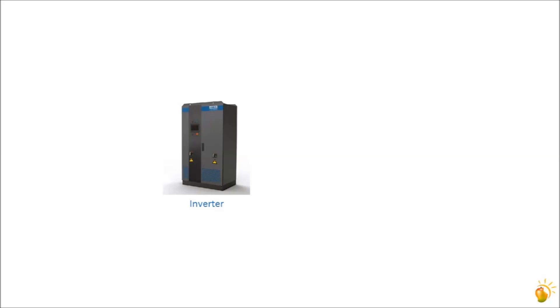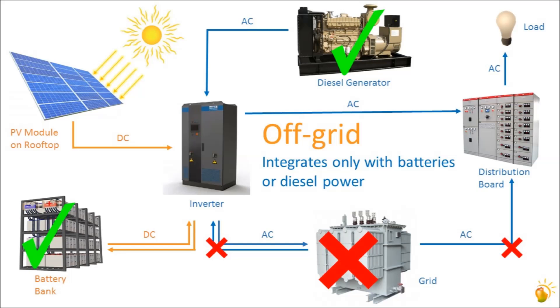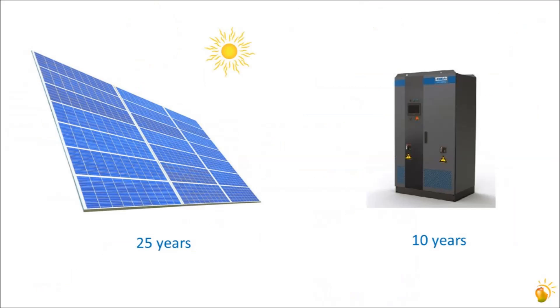The three types of solar plants boil down to three types of inverters: the grid-tie inverter that integrates only with grid power; the off-grid inverter that integrates only with batteries or diesel power but not with the grid; and finally the hybrid inverter that can integrate with grid power, diesel and battery power. A solar PV plant will last 25 years and the inverter can last 10 years or even longer. It is therefore important to choose an inverter keeping in mind both current and future requirements.